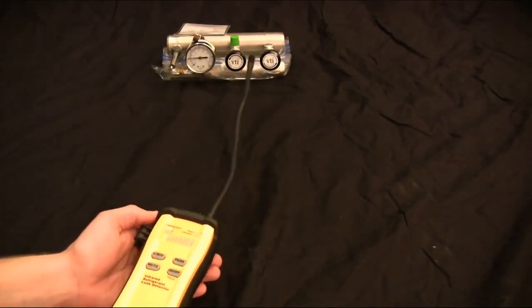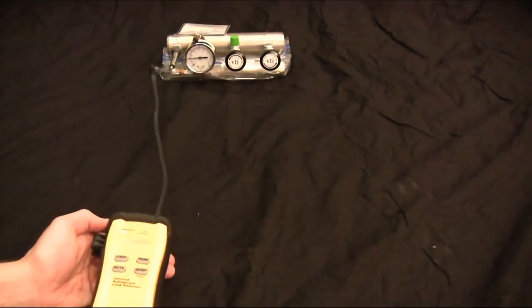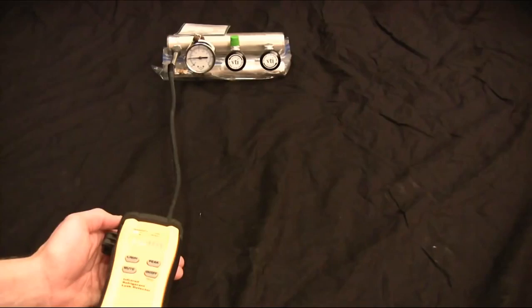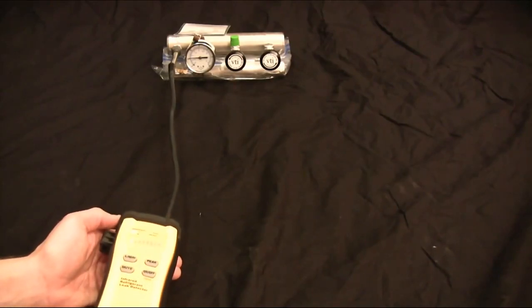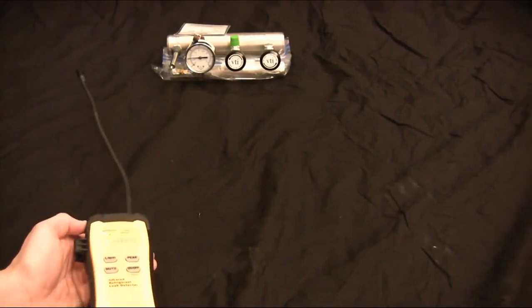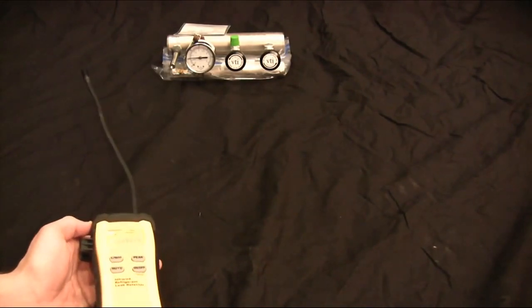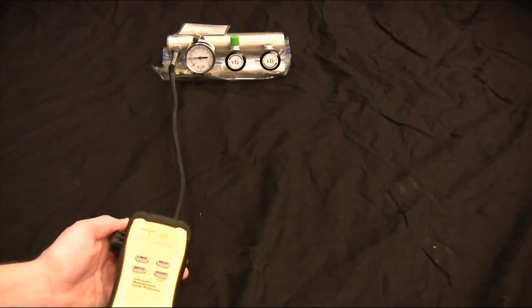You can see that it's a solid tone rather than a more fluttery tone. And this will also still stabilize to that lower refrigerant. You can see that this leak stabilizes a lot faster than the .31 ounces per year leak, just because this is a much smaller leak. But it's still only a few seconds and I can go right back.